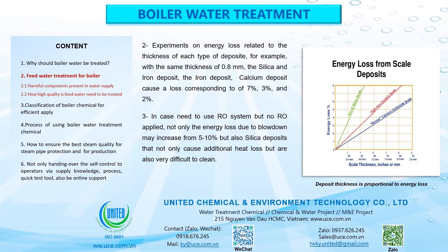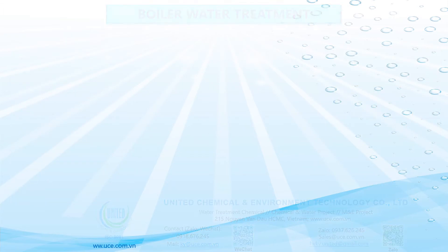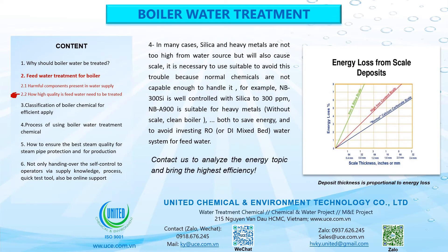2. Experiments on energy loss related to the thickness of each type of deposit show that with the same thickness of 0.8 mm, silica and iron deposits cause losses of 7%, iron deposit 3%, and calcium deposit 2%. 3. In cases where an RO system is needed but not applied, energy loss due to blowdown may increase from 5% to 10%, and silica deposits not only cause additional heat loss but are also very difficult to clean. 4. In many cases, silica and heavy metals may not be too high from the water source but will still cause scale. It is necessary to use suitable chemicals; for example, NB-300Si is well-controlled for silica up to 300 ppm, and NB-A900 is suitable for heavy metals — without scale and with a clean boiler — to save energy and avoid investing in RO or DI Mixed Bed water systems for feed water.